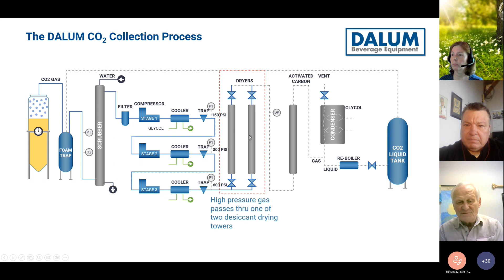Next slide. We go into dryers. One thing, at the temperatures we're going to be working at with liquid CO2, you don't want moisture in there. So we go through 2 desiccant dryers. In this case, let's say you're going through the left tower while the right tower is in regeneration. You regenerate with heat, electric heat, to drive off the moisture. But basically, it's taking the dew point of the gas down to, I think it's minus 62 F is what we get down to. Next slide.